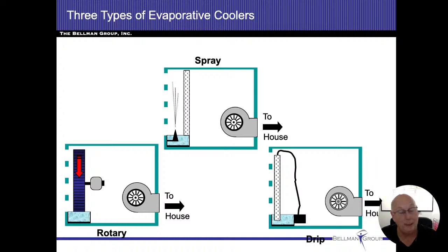We can't use them here in the Chicagoland area because our summers are very humid. And if we add more humidity to the air, we're just going to be even more uncomfortable. So we don't do it here. Other areas have problems with it. I mentioned Colorado earlier. They have such long, cold winters there, and the freezing temperatures would also create a problem.